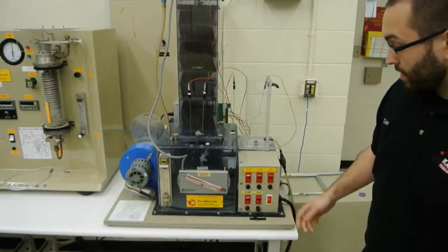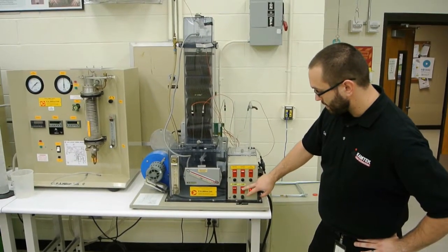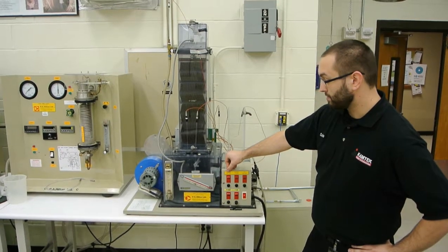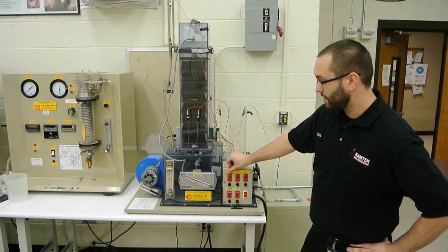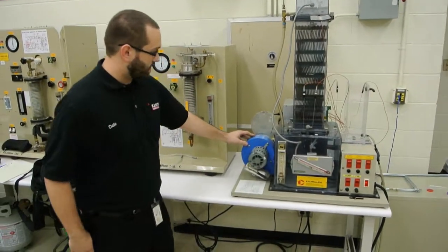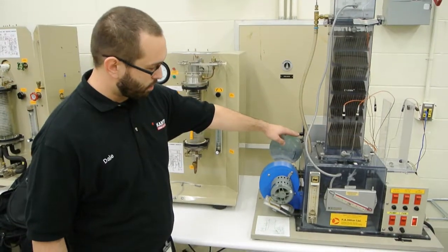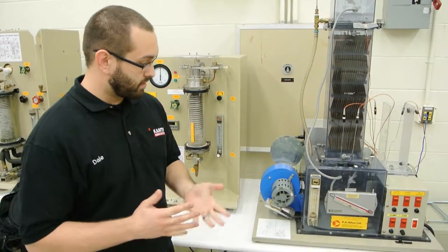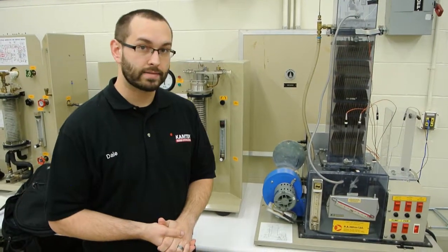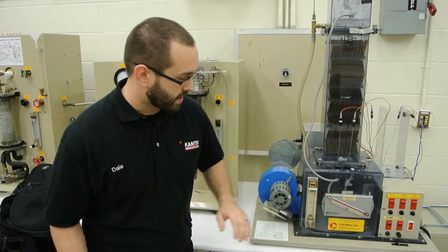To start the machine, once all the water is in there, you're going to turn the pump on, you'll turn the fan on, and for your initial setting, you're going to turn the heater to 0.5 kilowatts. Then you're going to come over here, and you'll make sure that your fan, which has this disc to control the airflow, is all the way open. That's going to be your initial setting, and you're going to wait for a steady state, which takes about 7 minutes. Once that happens, you're going to record your flow rate and the pressure from the air.